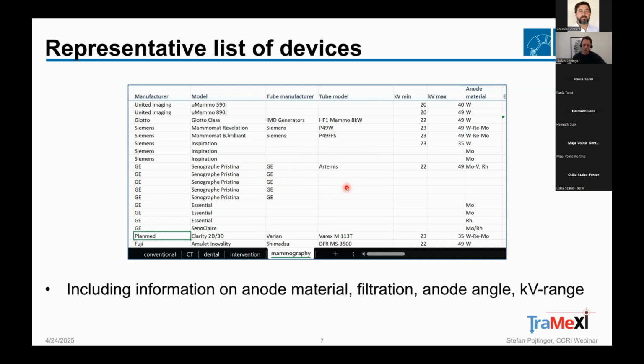And in addition to the names and the models of the devices, we were also asking for some basic information on the X-ray tube and also the filtration that is available at the devices. For example, we were asking for the material of the anode of the X-ray tube, the filtration, anode angles and kV range. And the reason we wanted to know the details for the devices was that if you have the knowledge about these quantities, you can calculate the HVL values for the energy range of each device.